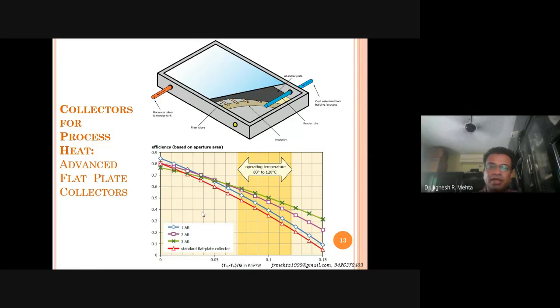So you have to improve the quality of the collector, and mainly it is highlighted, or one is talking about, the glazing or the glass cover. If this glazing has an anti-reflective coating, then it will improve the optical efficiency of a solar collector. So you can go on improving this, and it will give you somewhat higher efficiency when you want to use it at a higher temperature. For, let's say, 80 to 120, you can see that this green line collector with 3 anti-reflective layers of glazing may provide you the highest efficiency. When you want to use it for process heating applications, the temperatures are not as low as domestic water heating, so you have to use better quality flat plate collectors.